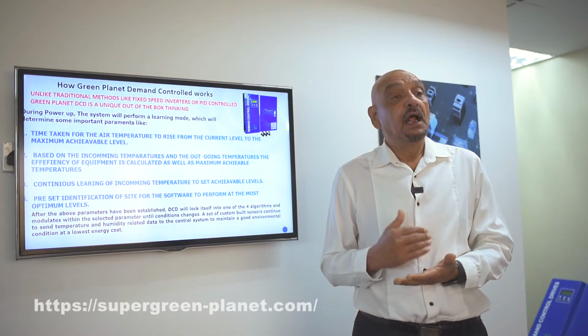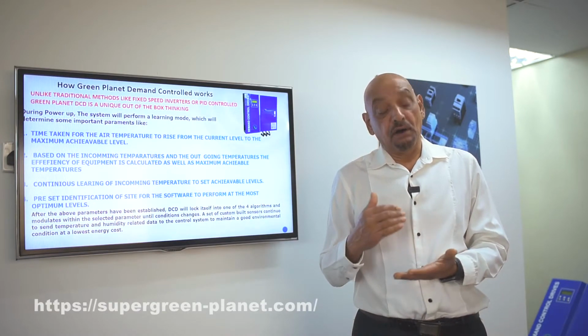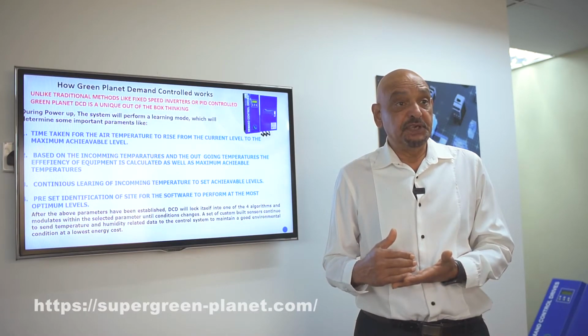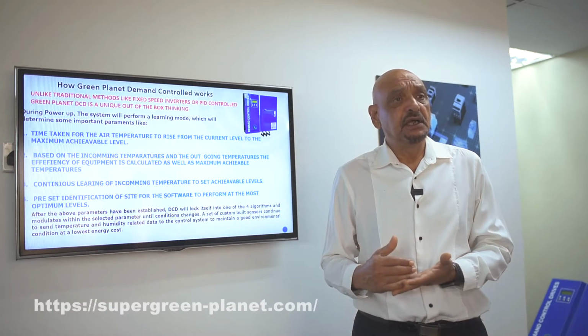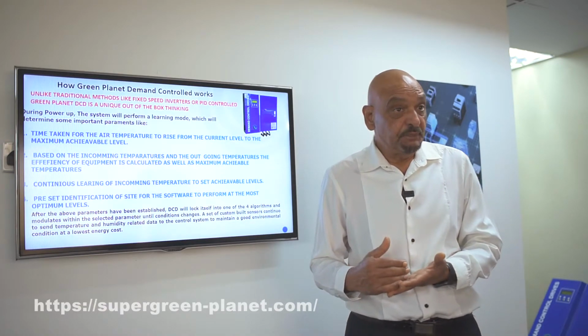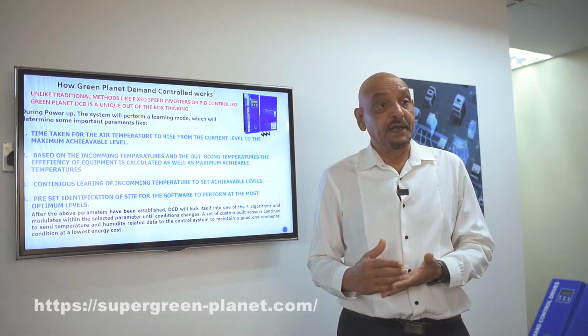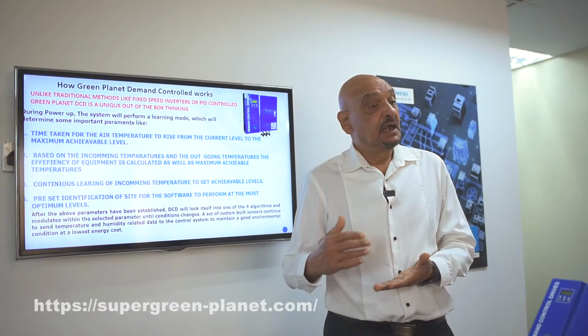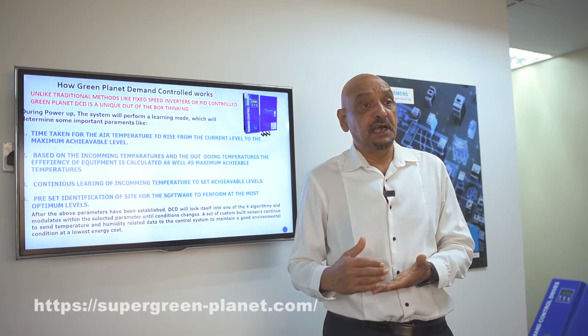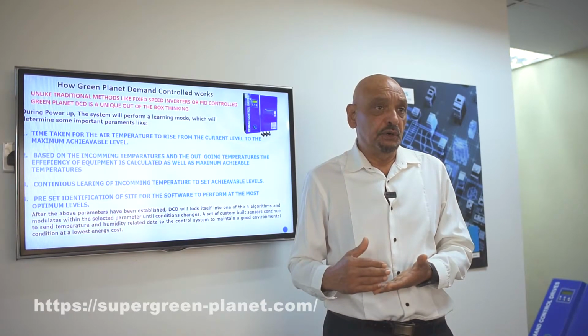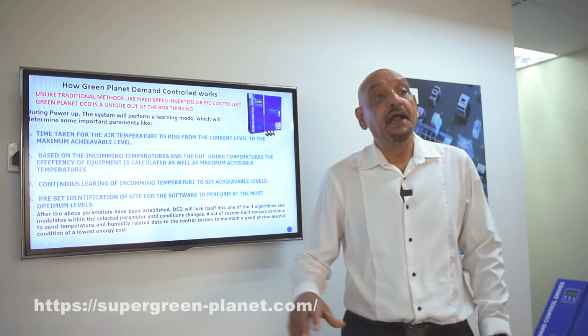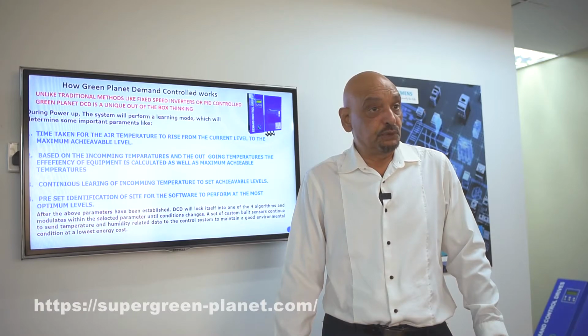Now, bear in mind, all the driving is done digitally, which means that there is no frequency fluctuation, just like what you may get within the PID system, right? Within the PID control system, you will find there is a lot of frequency fluctuation, which is not good for the motor, and also sends a lot of electrical noise into your system. So the DCD has been designed in such a manner that it will drive digitally and it will maintain a very, very fixed frequency all the time.